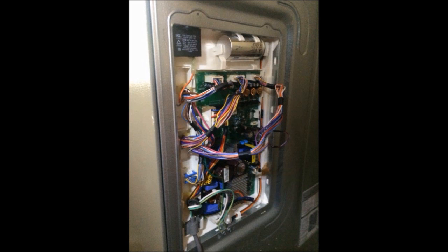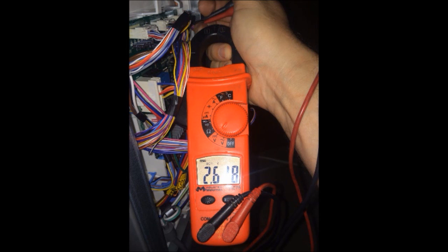Let's start off by checking pin 1 to pin 3. So what we're reading here is voltage, feedback voltage to the motor, and we have a registration here of 2.618. In this instance, when we do this test, if it is 0 or if it is 5, then we replace the motor. So this tells us that the motor is good.